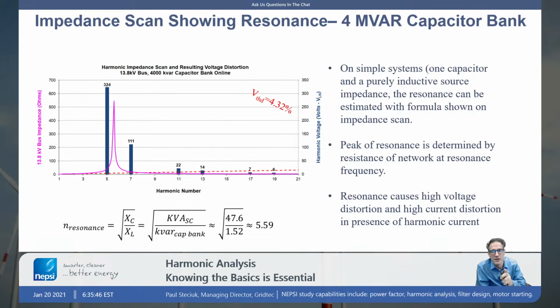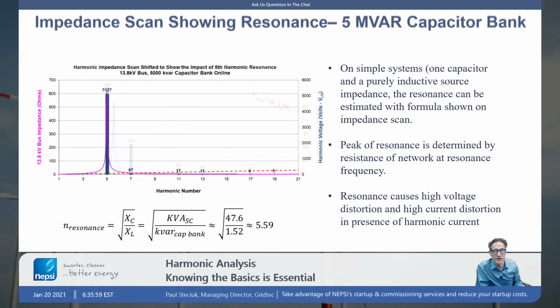I'm okay. But the reality is that we often do not know the system well enough. We don't know the system well enough, and the impedance curve could shift. Okay, could shift to the left. In this case, if it were to shift to the left, that current would then be injected times that impedance value of 600 ohms, and we would have a value of 5,127 volts. So 64% voltage distortion, so unacceptable.